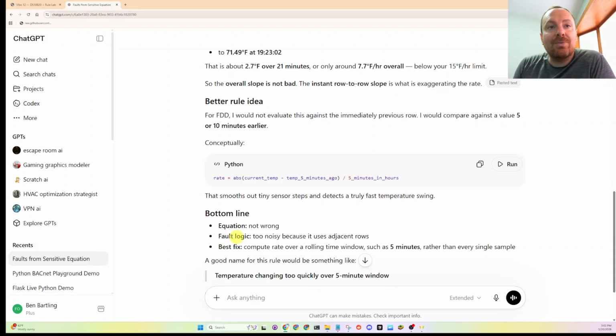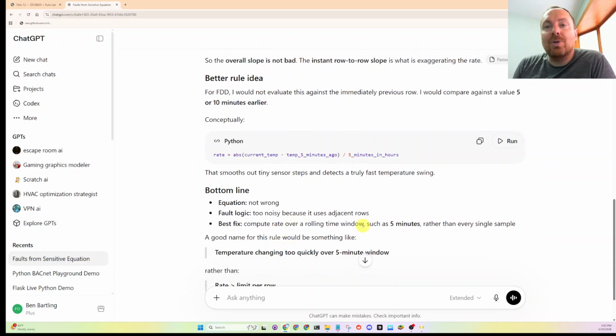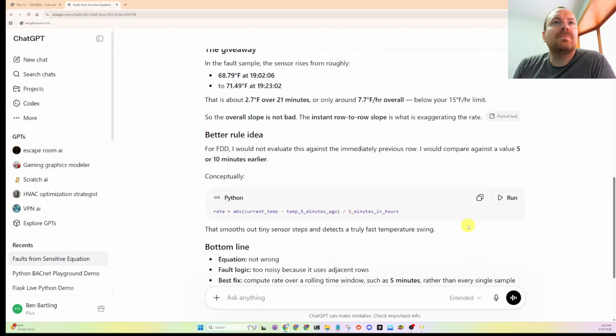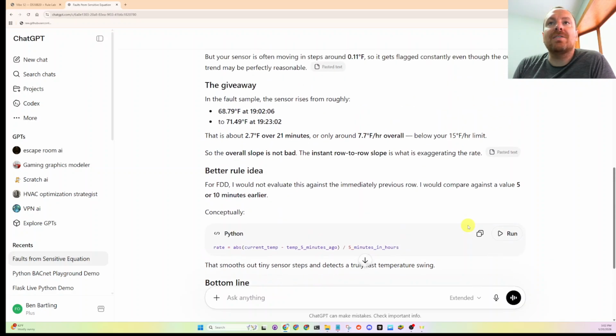Okay, so the equation is not wrong. The fault logic is too noisy because it uses adjacent rows. Best fix, compute the rate, over a rolling window such as 5 minutes, rather than every single sample. So we'll get into that later. That's something that's coming, they're covering rolling averages of data.